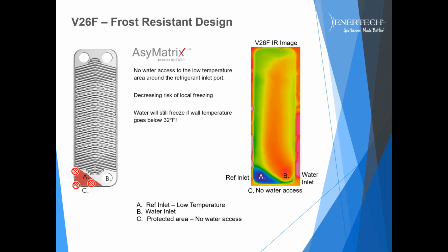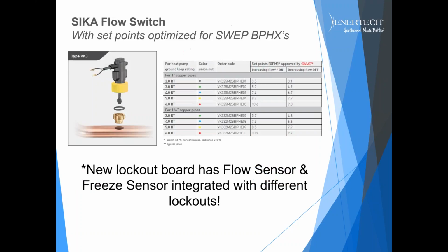Okay, moving on. The flow switch, again, I mentioned this. We're working with Sika on the flow switch, and again, it's optimized for SWEP's braze plate heat exchanger as well as Enertech's horizontal heat pump. And the flow switches are all different flow settings based on the tonnage of the unit and the minimum flow that we can see with that product to ensure that we don't have any freeze issues. So the flow switch is not just a standard flow switch across the product. And again, our new lockout board has both flow and freeze sensors integrated within that lockout strategy just to make sure that we're not going to have any issues.